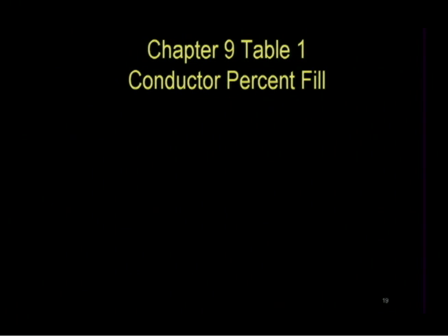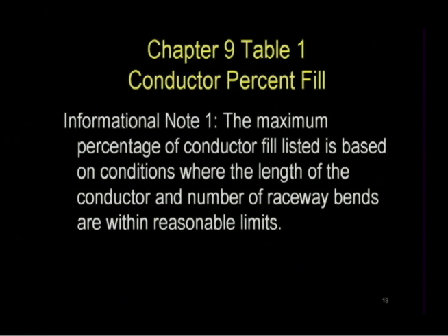Okay, we're still on Chapter 9, Table 1, the conductor percent fill. There's an informational note. The maximum percentage of conductor fill listed is based on conditions where the length of the conductors and the number of raceway bends are within reasonable limits.